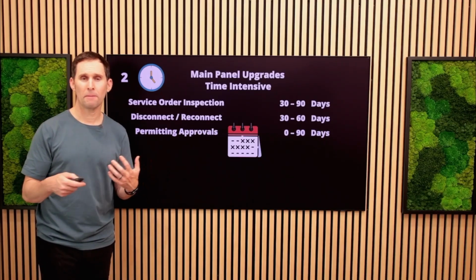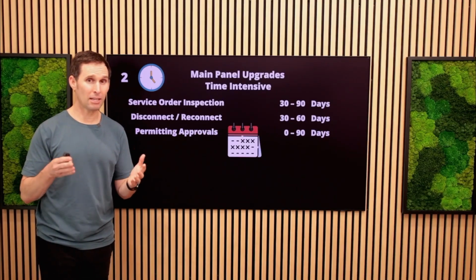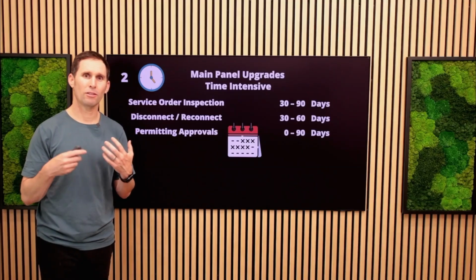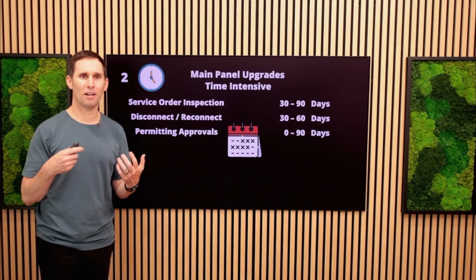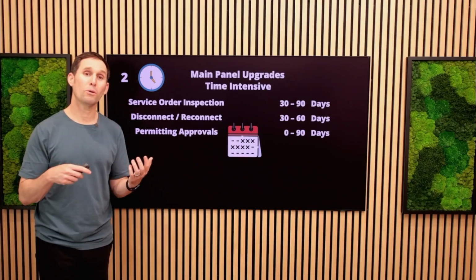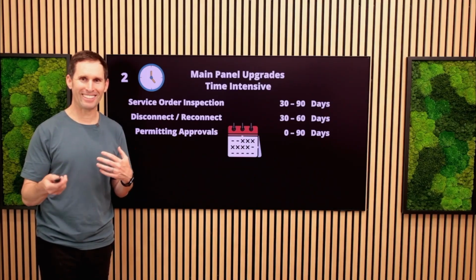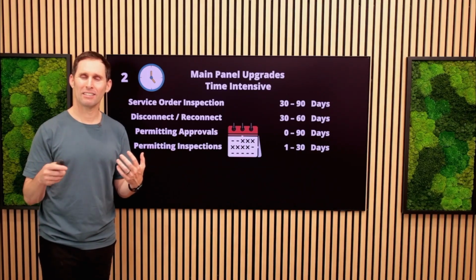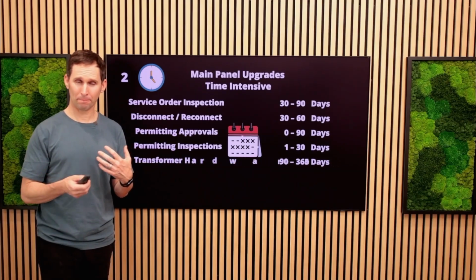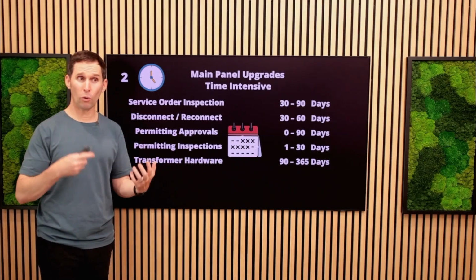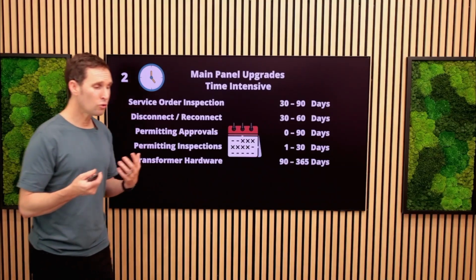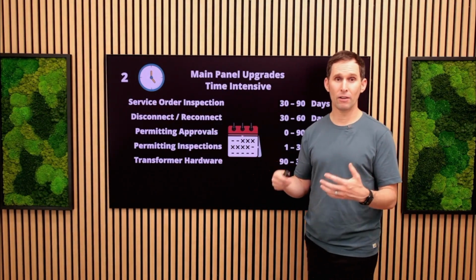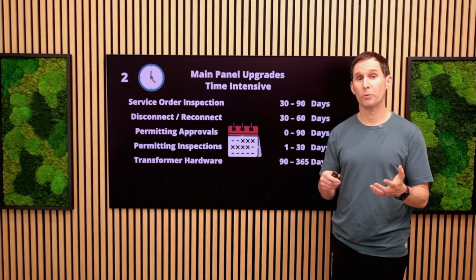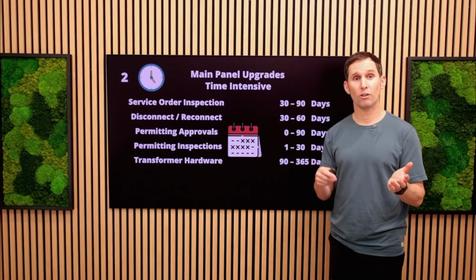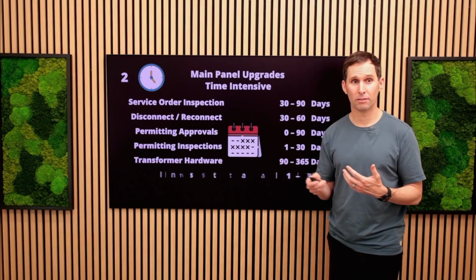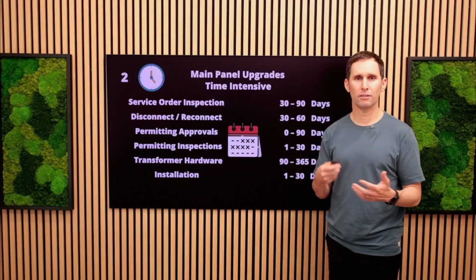Now a permit needs to be designed and approved — sometimes that can be done in parallel, and it can add another few days up to 90 days if the local authority having jurisdiction has a delay. The permit inspection needs to be scheduled, which sometimes can take a long time. If a transformer needs to be ordered to increase the total supply to that region or neighborhood, there's a worldwide transformer shortage that can take up to a year, or even beyond that — I've seen up to 2 years. Then the installation itself could take a few days to a month.